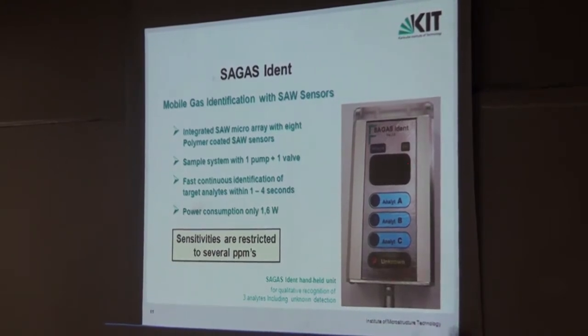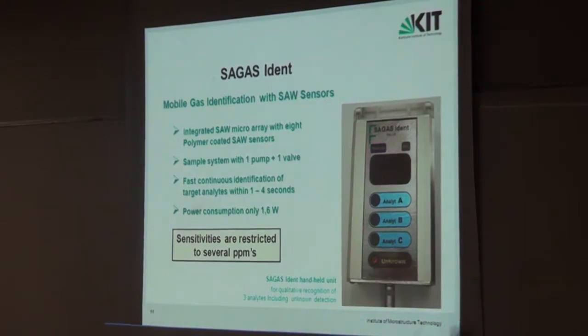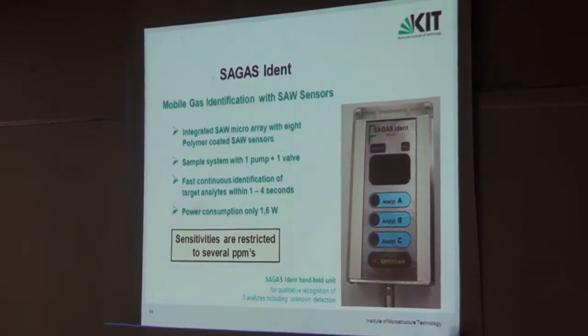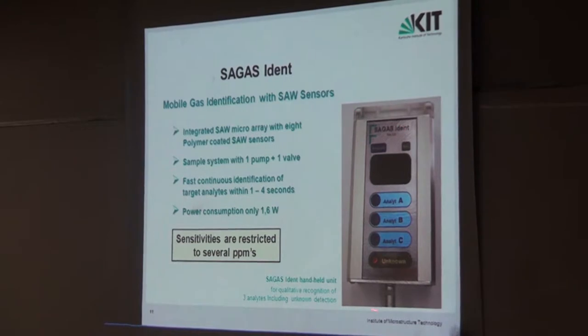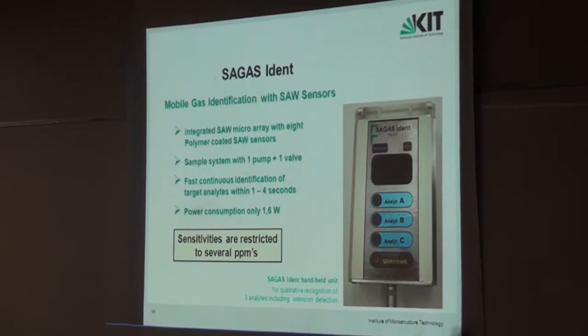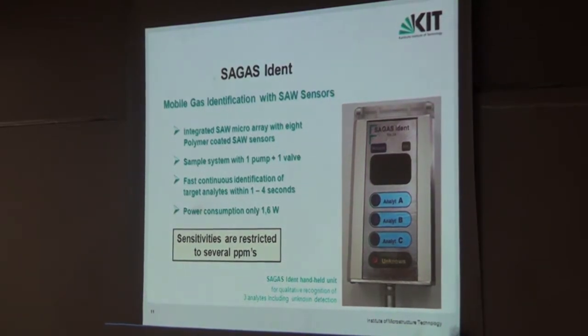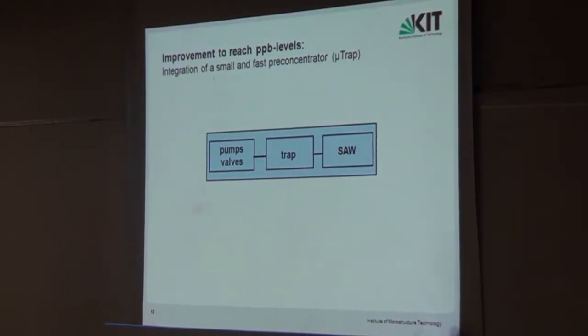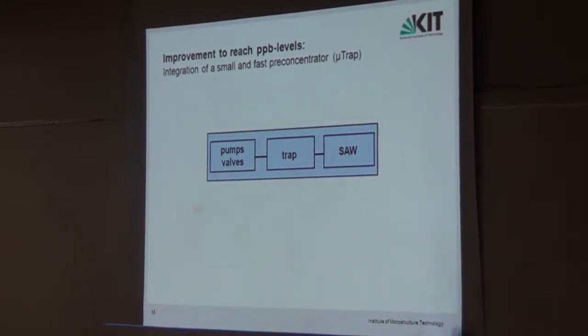However, without further sample treatment, sensitivity is restricted to several PPMs only. We cannot reach the very interesting PPB level, where some toxic gases may already exceed workplace limits. This is a restriction — the instrument as-is is good only for simple identification, such as checking whether a tank has been cleaned or contains residual solvents. To reach the PPB level, we need a sample preparation step, and here we introduce a pre-concentrator called a micro trap.